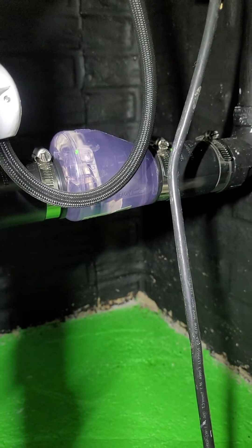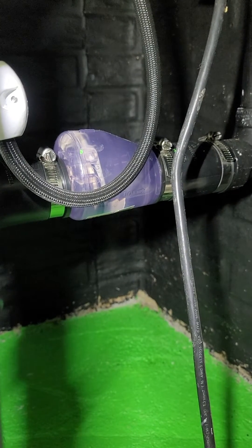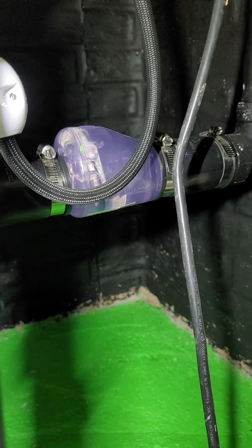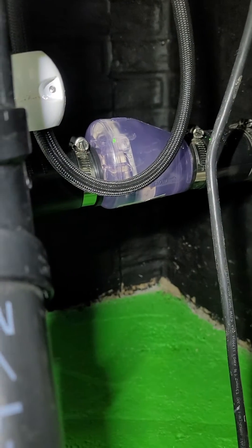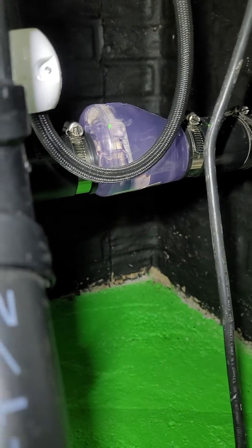So this is what I got instead — that handy little device right there, known as a quiet check valve. I picked it up from Lowe's and it has totally prevented my water hammer issue. I don't get the knocking or banging noise anymore, and it's easier on the pipes and the pump.